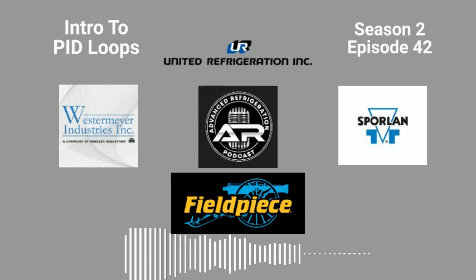Now, when you are looking at this stuff, you need to look at trends over time. So you need to be watching this. PID tuning could take all day. You could spend 8 hours tuning one loop. It takes time. It's like 15, 20 minutes in between adjustments. You could spend 8 hours adjusting and it'd still be wrong.